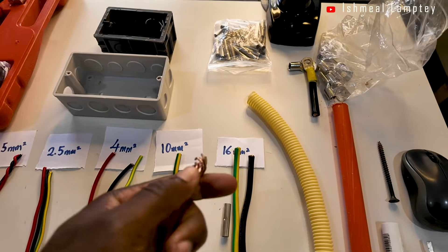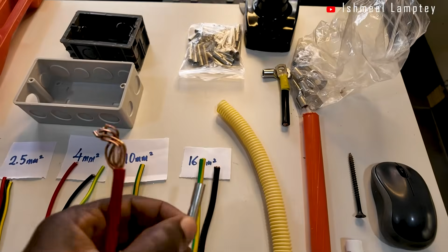And then we have this material over here, which is known as ferrules. This ferrule is basically used to connect 2 cables together. So imagine you want to connect these 2 16mm cables. Because 16mm cables are usually hard in nature, it will be difficult to connect them together, although some people do it, which is not proper. That is why there are tools or materials like this. You twist the cables, or you take off the coating of the cable, you pass it in this material, and then you use your crimping tool to crimp it, and that is going to hold it very firm and tight, as against just putting the cables together.